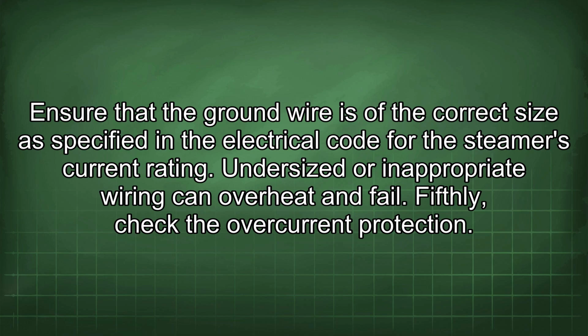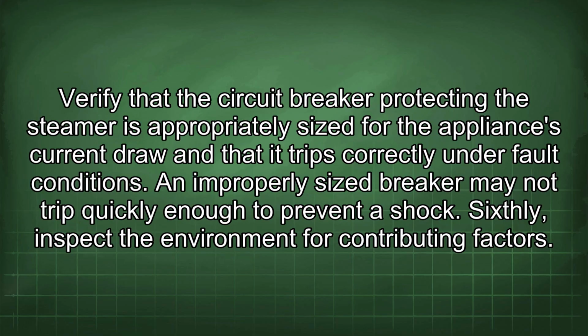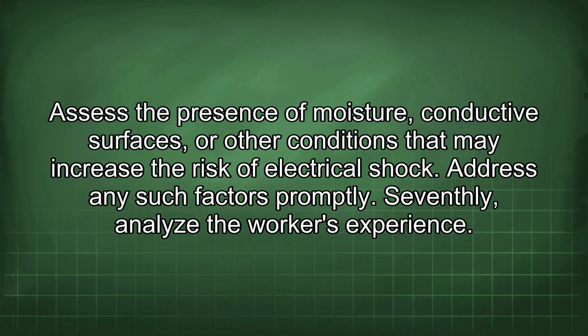Fifthly, check the overcurrent protection. Verify that the circuit breaker protecting the steamer is appropriately sized for the appliance's current draw and that it trips correctly under fault conditions. An improperly sized breaker may not trip quickly enough to prevent a shock. Sixthly, inspect the environment for contributing factors. Assess the presence of moisture, conductive surfaces, or other conditions that may increase the risk of electrical shock. Address any such factors promptly.